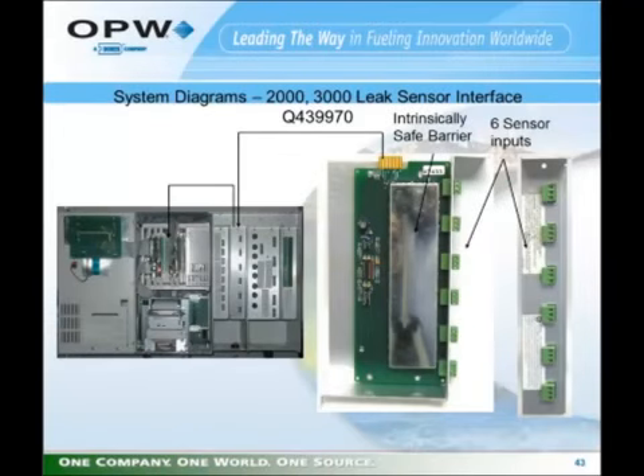The leak sensor interface module is distinguishable by 6 connectors for 6 sensor inputs. There can be a total of 4 interface modules installed in the unit for up to 24 sensors. Module 1 and 2, or sensors 1 through 12, would connect to a cable that goes to leak sensor driver board number 1, and the second 2, for sensors 13 through 24, would connect to a cable that goes to leak sensor driver board number 2.